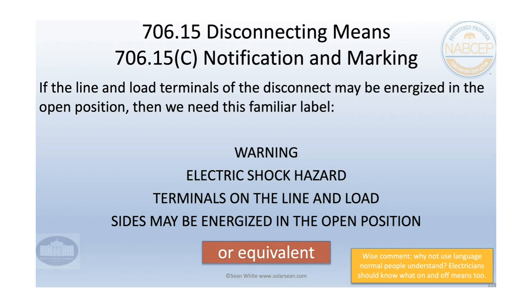Inverters that go to the grid do anti-islanding so fast, it's faster than a human muscle can move and touch an energized wire. And so you don't need this on the AC side of an interactive inverter. But between a battery, an inverter with a charger and things like that, or even a DC disconnect that has rapid shutdown, you still might want to put it there, like even for, say, SolarEdge or something like that, because with rapid shutdown, 30 volts in 30 seconds, so up to 30 seconds, you could still get shocked.